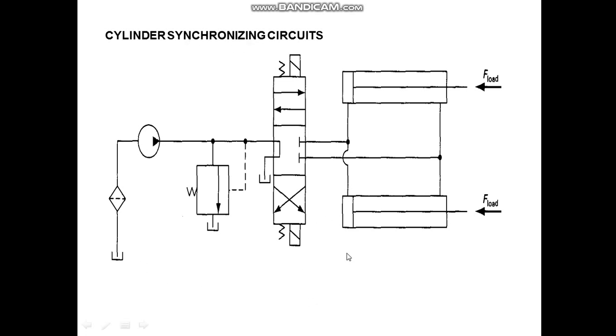The first arrangement to achieve synchronization is to connect multiple cylinders in parallel. We have two double-acting cylinders connected in parallel. Port A is connected to the blank end of cylinder 1 and cylinder 2, and port B is connected to the rod end of cylinder 1 and cylinder 2 at the same time. Let us see the working of this circuit.